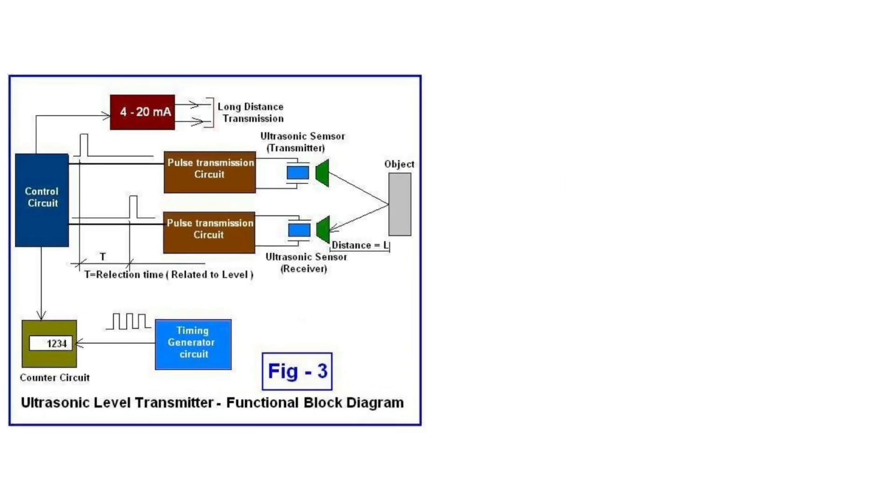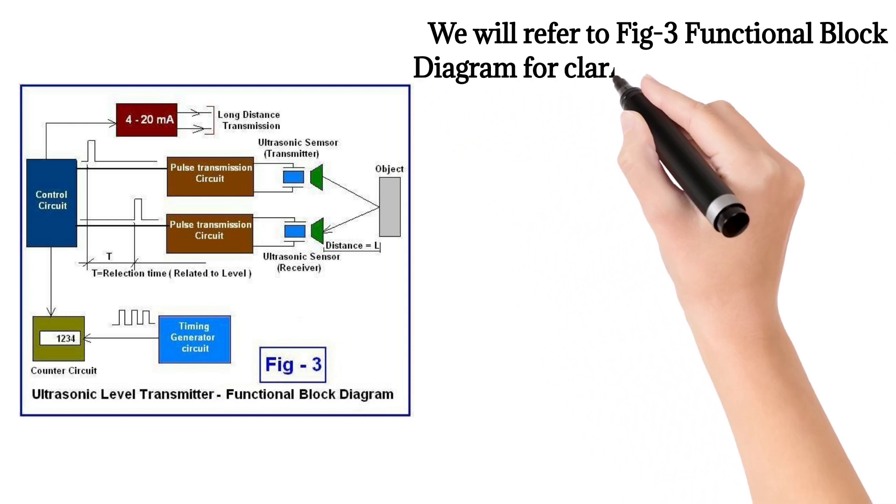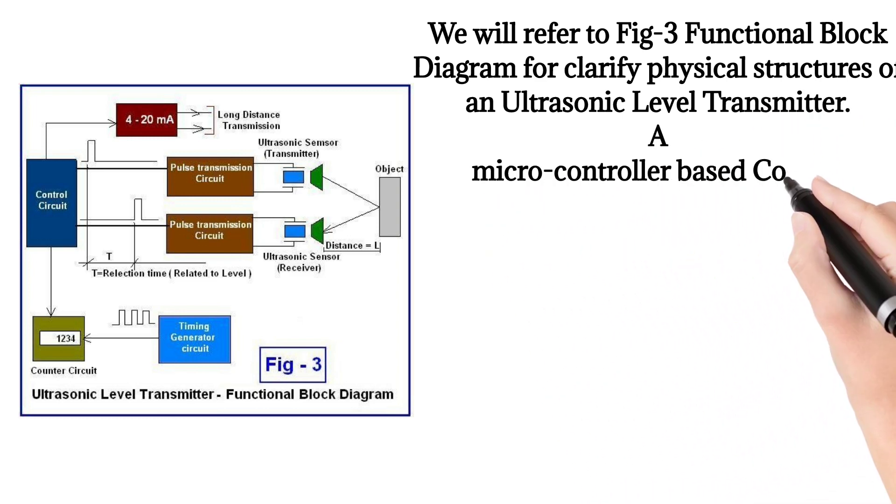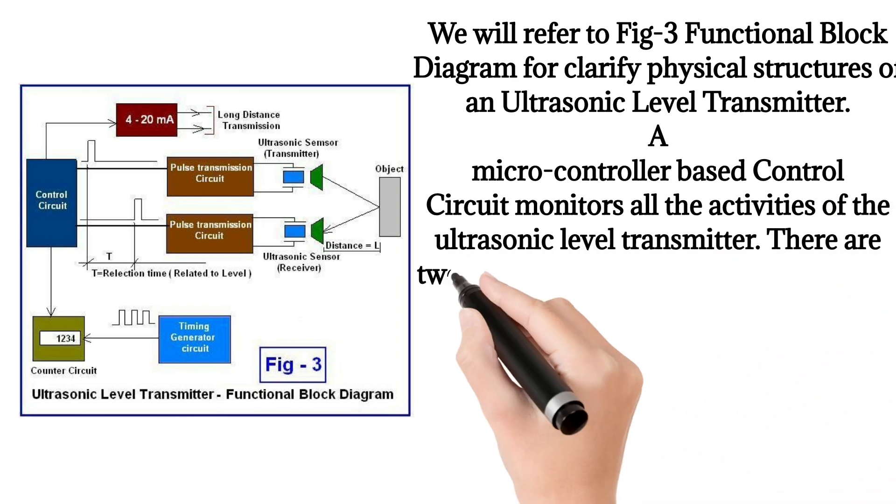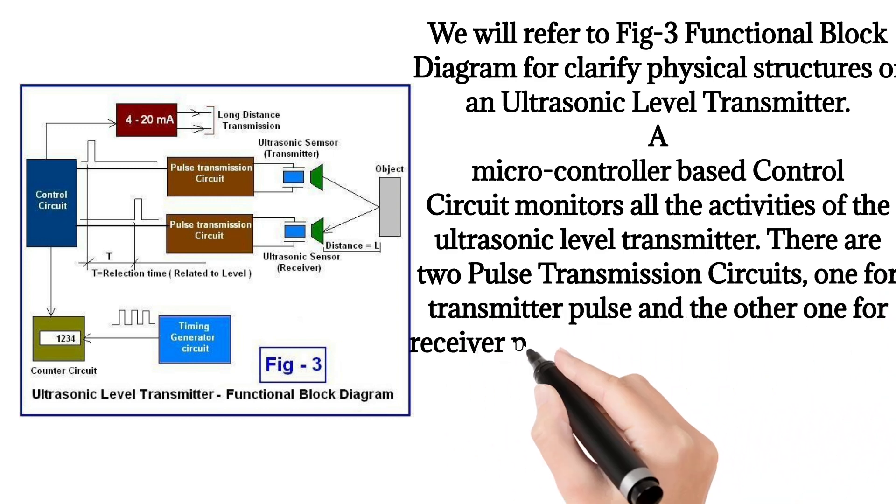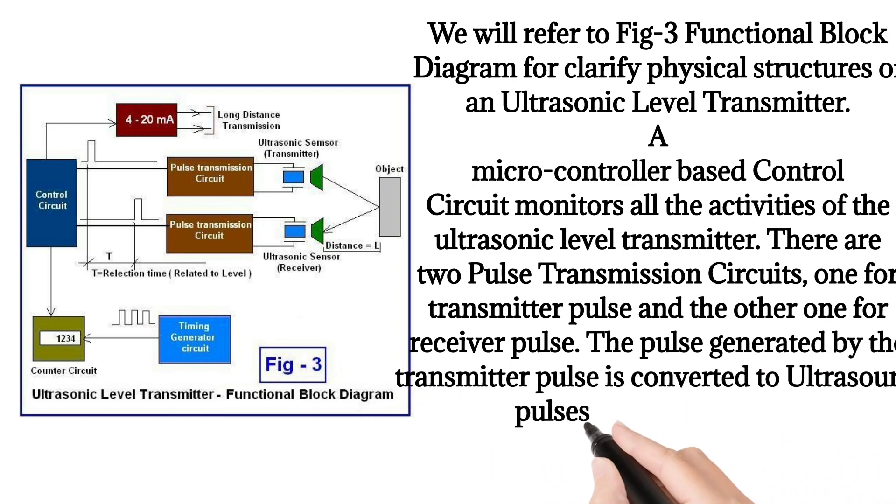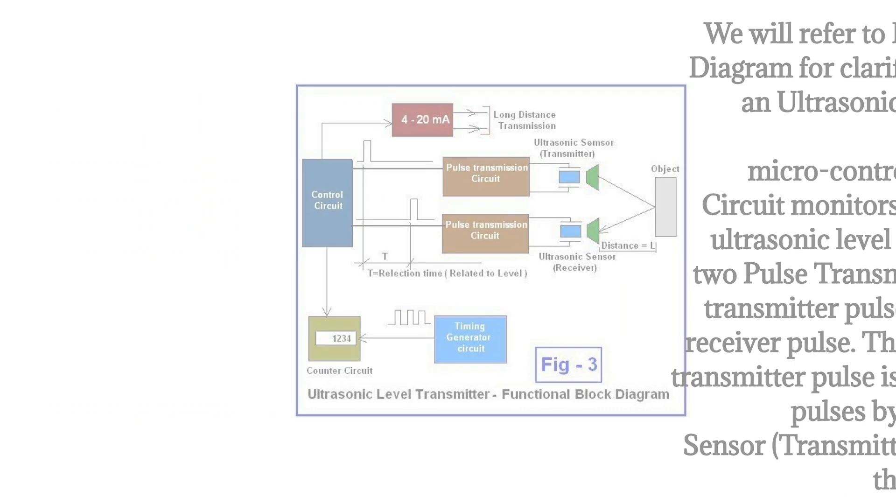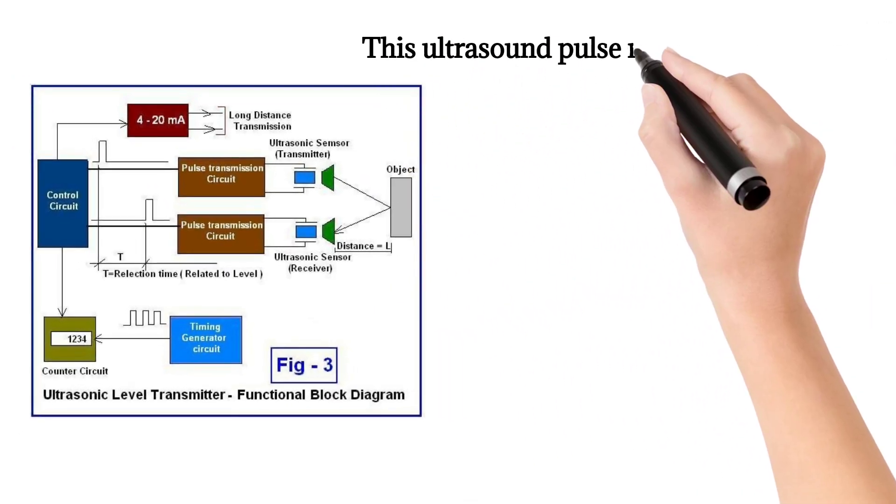We will refer to Figure 3 functional block diagram to clarify physical structures of an ultrasonic level transmitter. A microcontroller-based control circuit monitors all activities of the ultrasonic level transmitter. There are two pulse transmission circuits: one for transmitter pulse and the other one for receiver pulse. The pulse generated by the transmitter is converted to ultrasound pulses by the ultrasonic sensor transmitter and targeted towards the object.